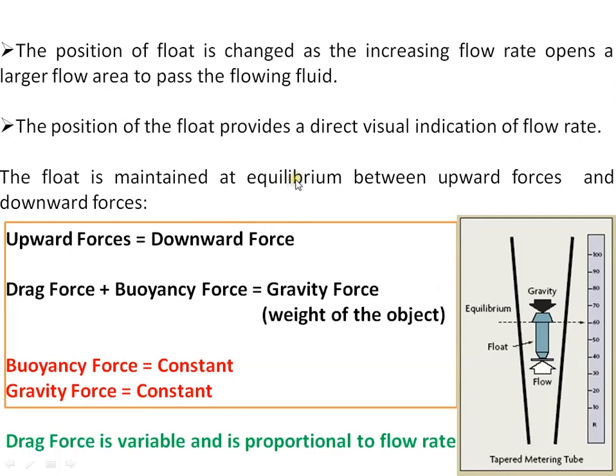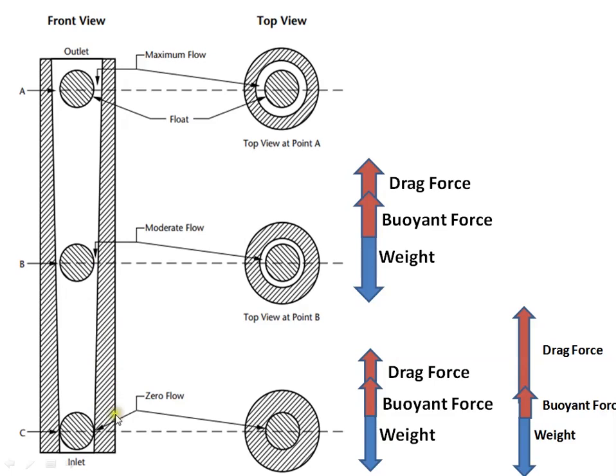At a particular position of the float it reaches equilibrium, where the upward forces equal the downward forces. The upward forces are two: drag force and buoyancy force. The downward force is gravity. Buoyancy force and gravity force are constant; the variable parameter is the drag force, which is proportional to the velocity of the flowing fluid. At the equilibrium position the area between the float and the tapered glass tube produces a balance of all forces.